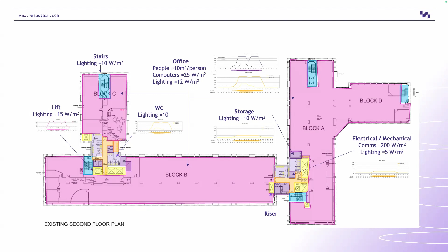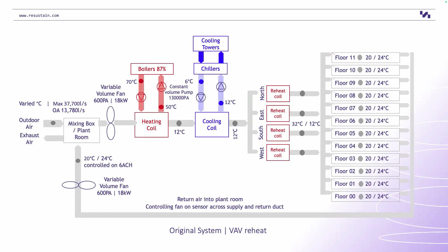Then we looked at the HVAC. And this is normally in the UK, I found, where a lot of the modelling stopped. But this, I think, is the most interesting part of it all, so I hope people will model this more. Essentially, you build out the air handling unit. In this case, the original air handling unit was a VAV system. It had boilers, chillers, cooling towers. It had reheat coils in each of the four risers going down the building, north, south, east, west, to release the air, and then it had dampers on each floor. It had a return duct, and then out into the world. So this was a retrofit.